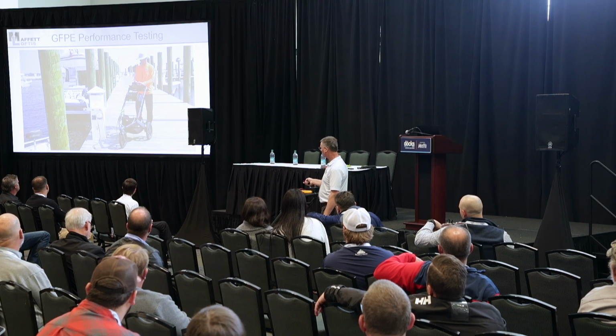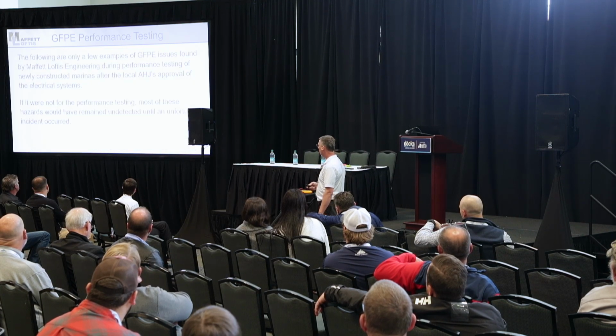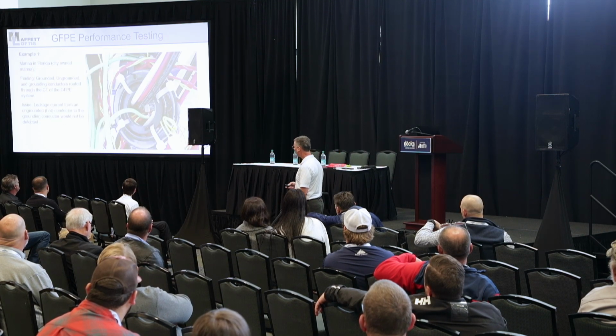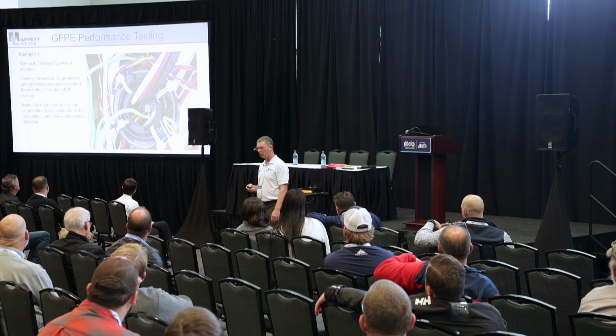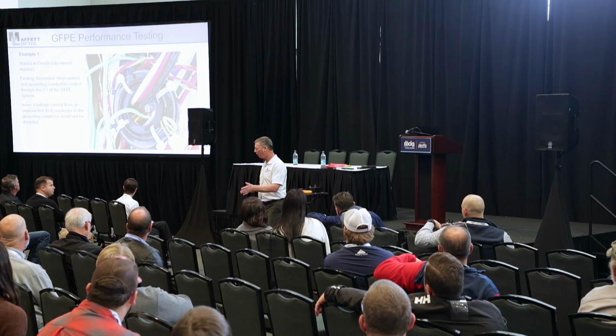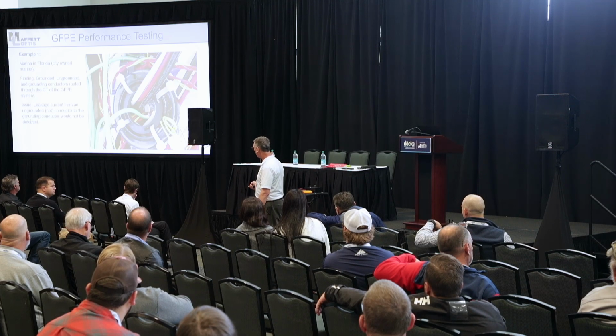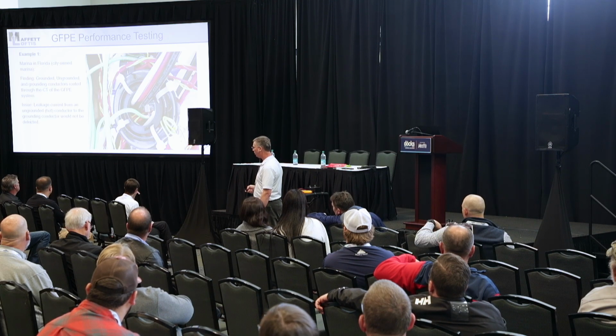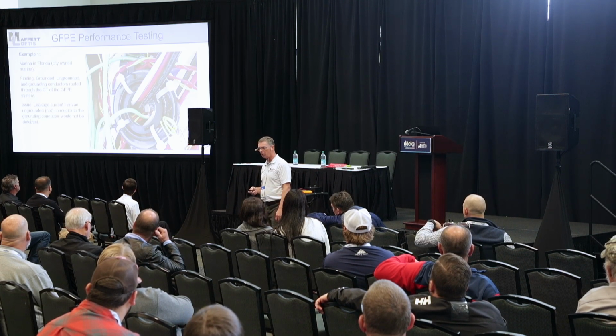Again, every single GFPE point is tested. I don't have time to go through this, but some of the things I find in marinas, even though it's already been passed by the electrical inspector — the green wire should never go into that CT where it measures the current.